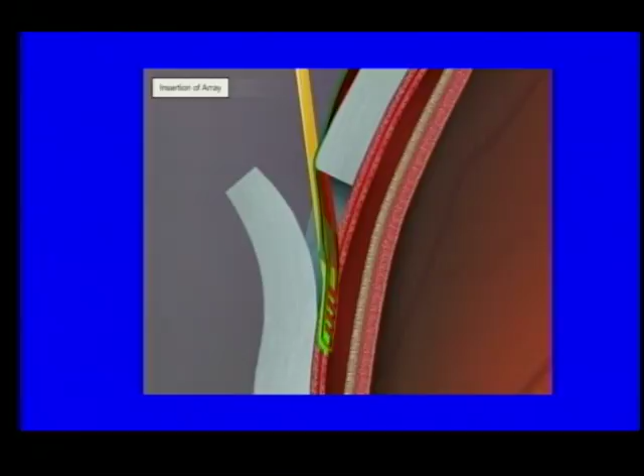So let's look at the function. This was the first such device we made many, many years ago. The whole thing was made on this 12-micron thick polyimide. So we made a device that was completely flexible, that we could suture around the eye. You could see the suture loops. It had its secondary coils, the custom-designed computer chips, and we were able to deliver power and data, which then went to the computer chips, which then delivered a signal to the electrode array. Back then, that was our first device, which was only 16 electrodes. That was probably 20 years ago. And that's what it looked like.